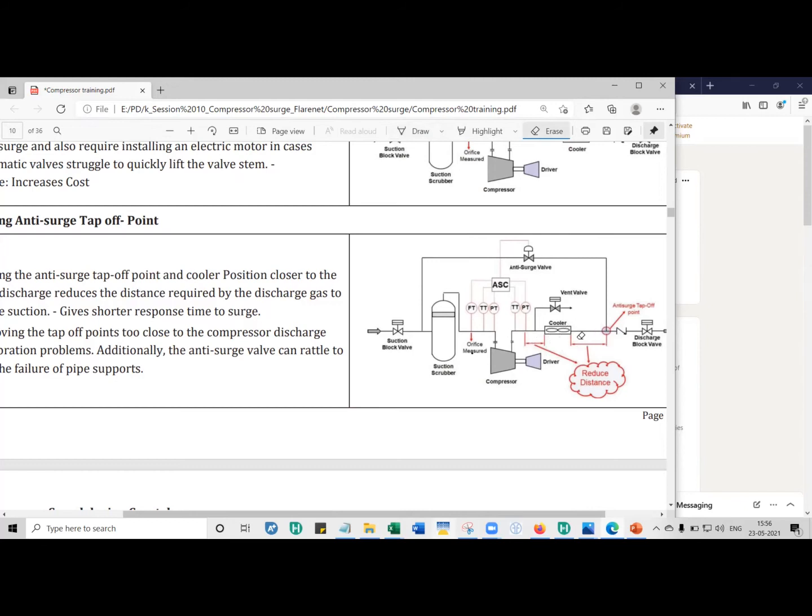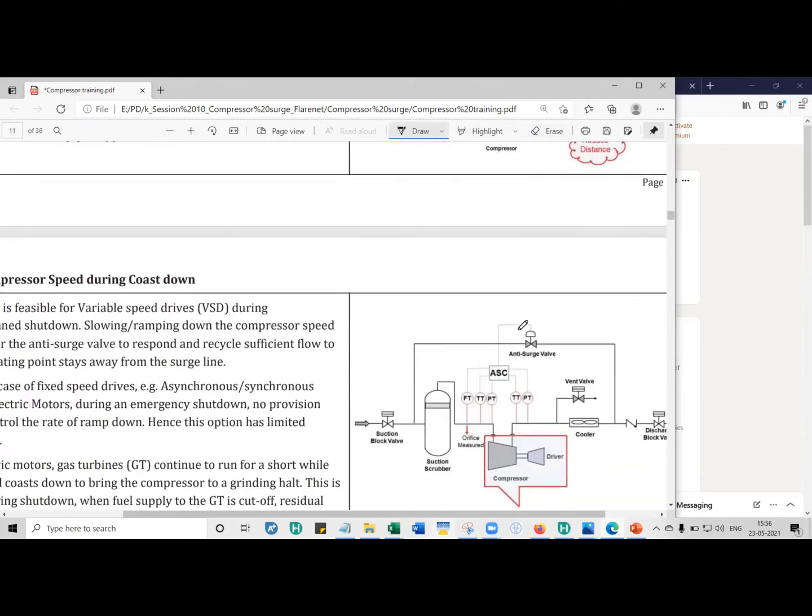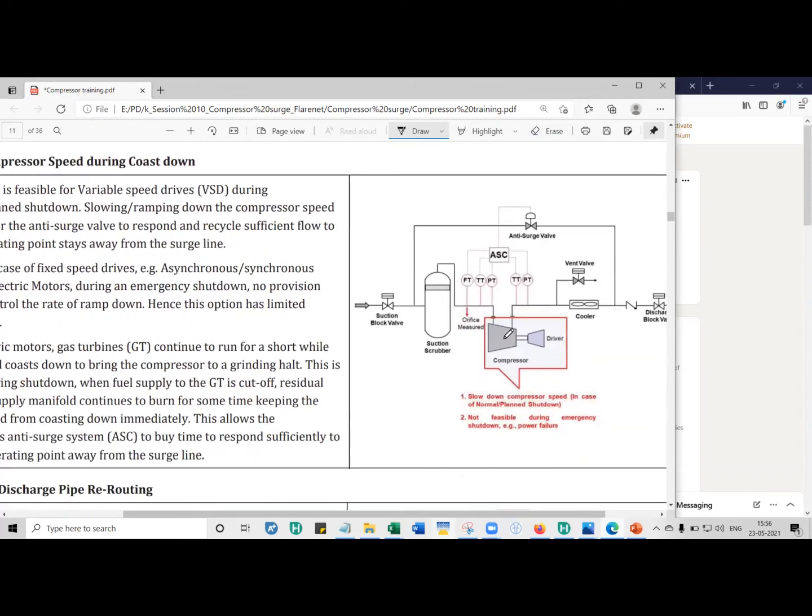If that is the case, try to reduce the piping distance. However, there is a limit to how much you can reduce it — if you move the cooler too close to the compressor discharge, you can have vibration issues. The louvers on the cooler, the cooler frame, and the pipes can all vibrate, and that vibration is transmitted to the anti-surge valve. So we do not want to push it too close to the compressor discharge.